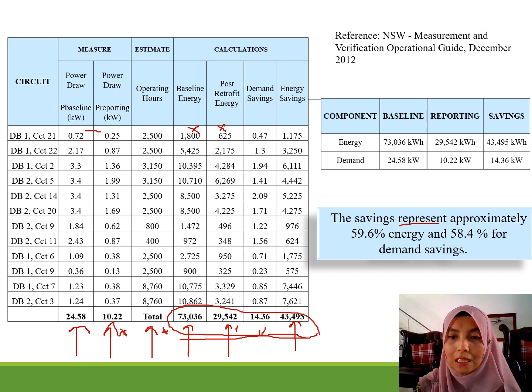Demand saving is the difference between the baseline power draw and the reporting power draw. Energy saving here is equal to baseline energy minus post retrofit energy. So we total up the energy saving, and the savings obtained here are approximately 59.6% energy and 58.4% demand saving.